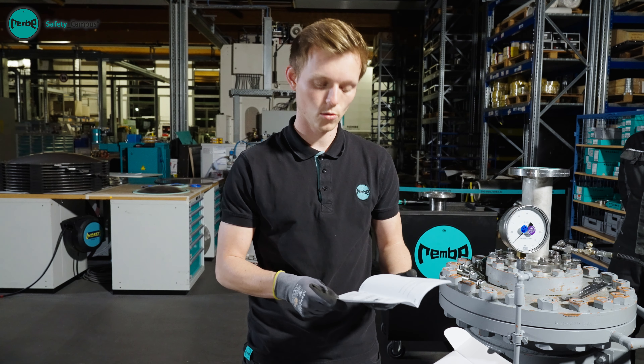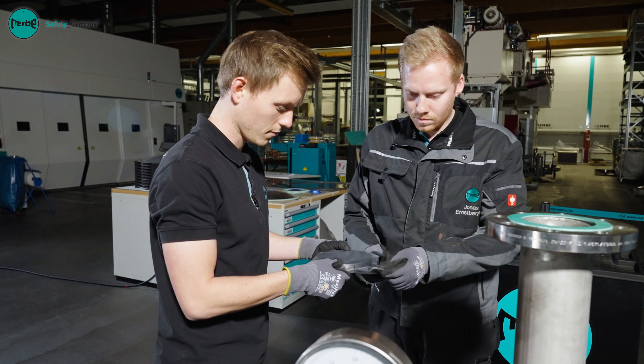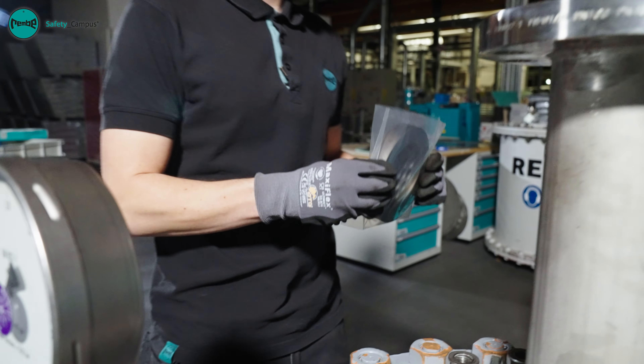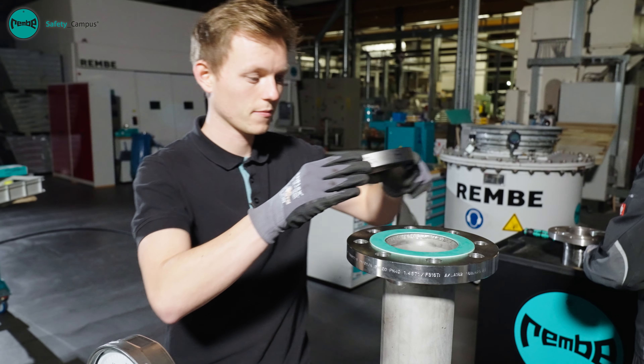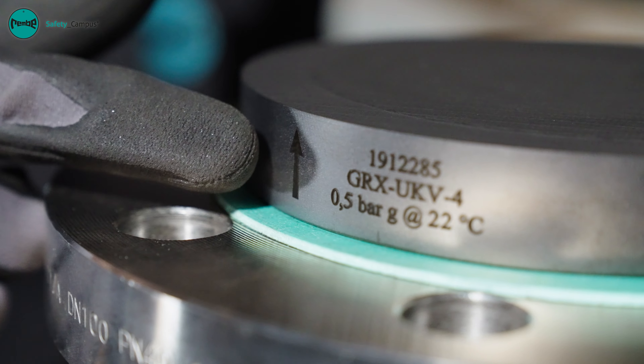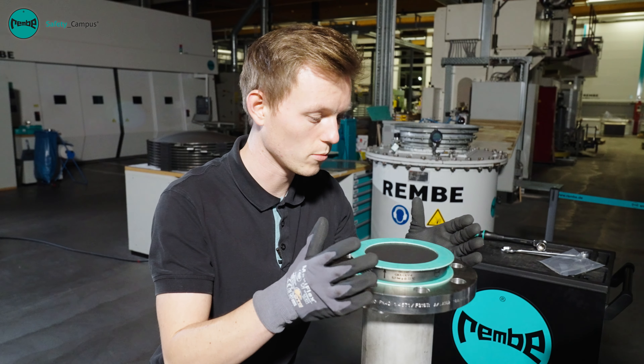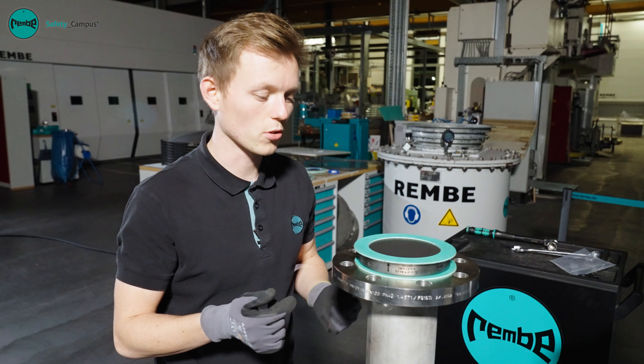When handling the rupture disc, it is important not to damage the sensitive sealing membrane. If the rupture disc is in perfect condition, we can begin with the installation. The protective film of the rupture disc should only be removed shortly before the installation. The direction arrows on the rupture disc indicate the correct installation direction. The gasket should be checked before use for scratches and damage. Damage could otherwise cause leaks in the process.